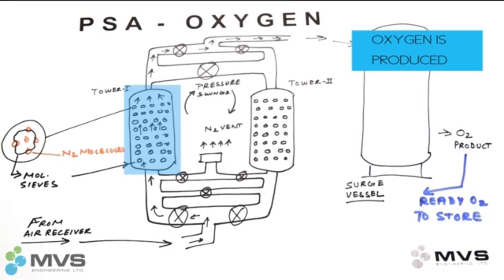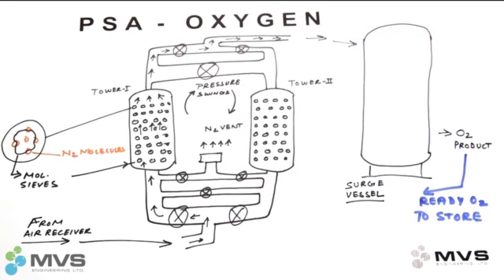Then we switch over to tower two, which gets pressurized by compressed air and starts producing oxygen. Meanwhile, tower one is depressurized and the nitrogen molecules are released back into the atmosphere through a vent port. Product oxygen from both towers is collected in an oxygen surge vessel.